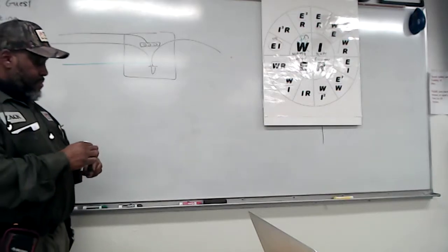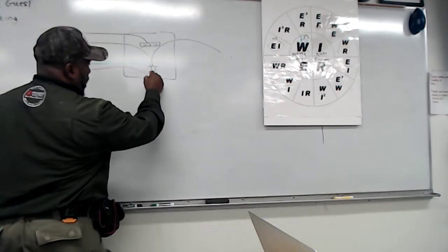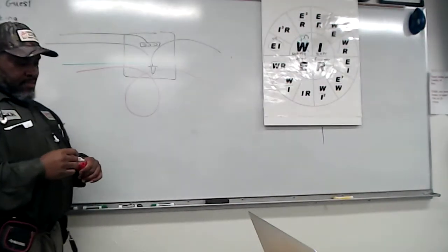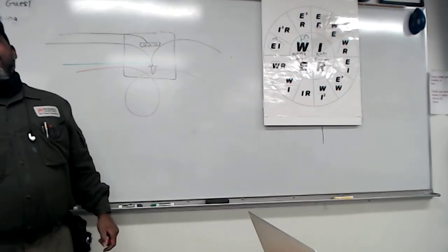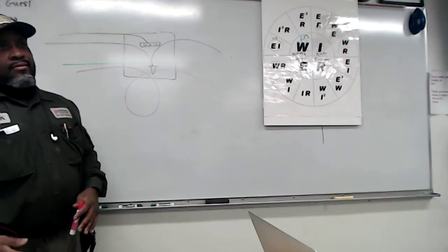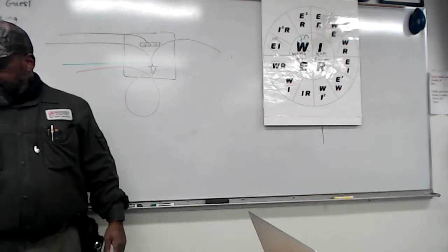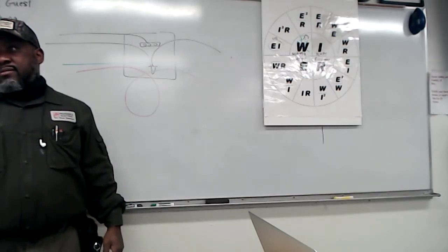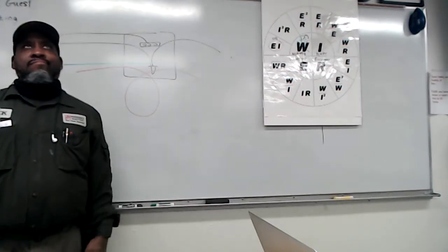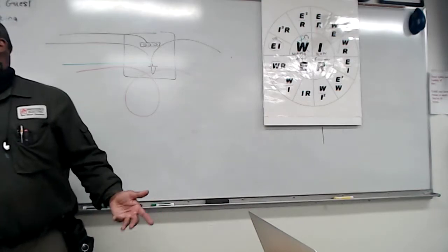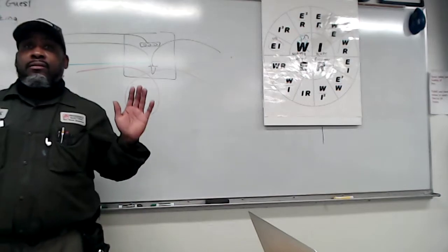Then it says, same rule number 1, if it's looped, it gets counted how many times? Twice. But how long does that loop have to be? 12. 6 and 6, right? Sometimes people put loops in the box, just extra wire. Okay, that's rule number 1.